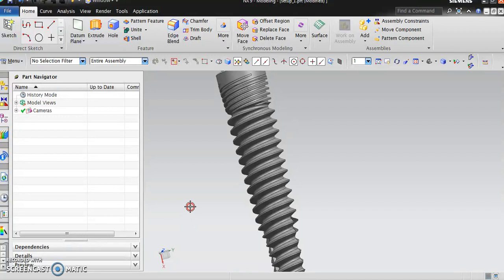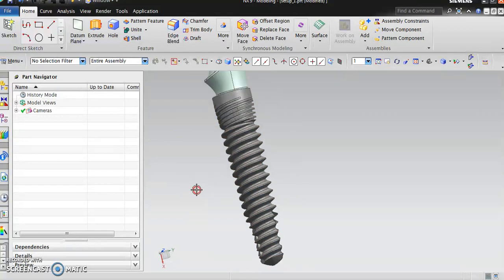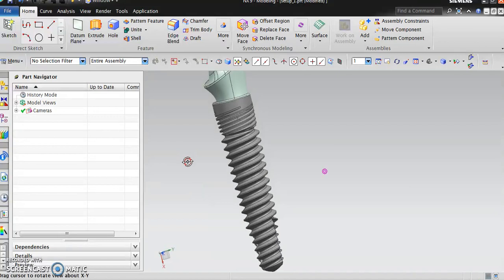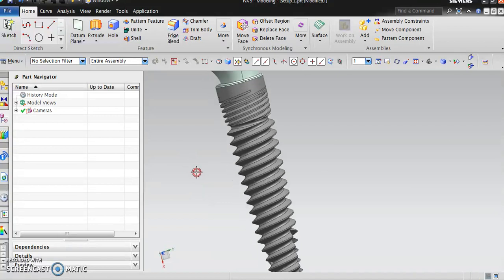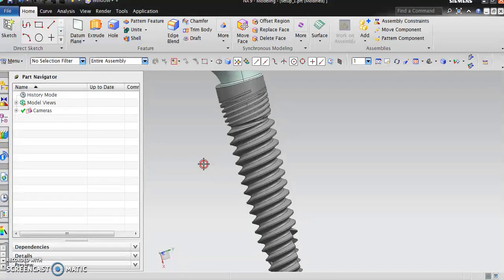The loading flank will prevent the screw from being pulled out due to the axial load. If you want a stronger force to resist the pull out on the axial load, you can use the buttress threads. Most of the common dental implants are made using the buttress threads.